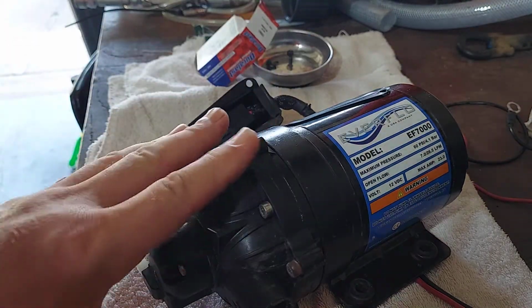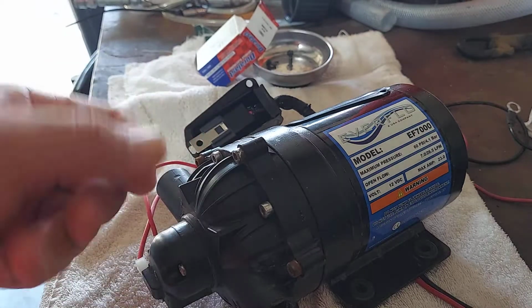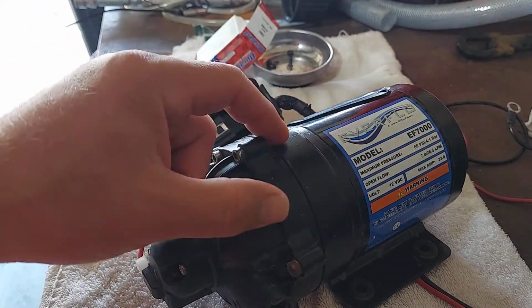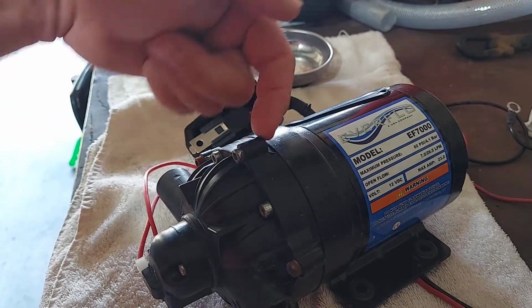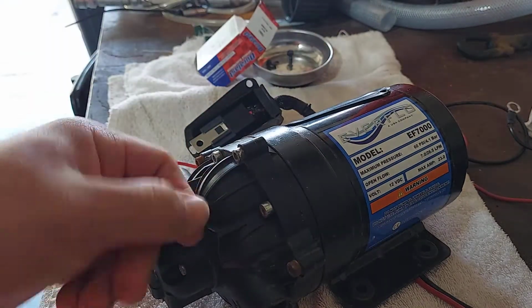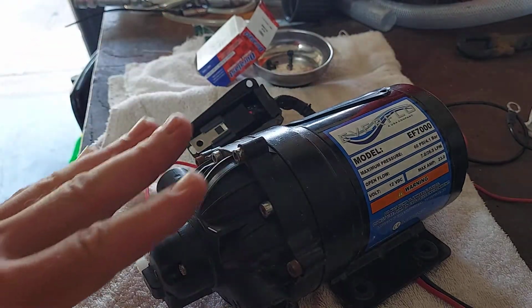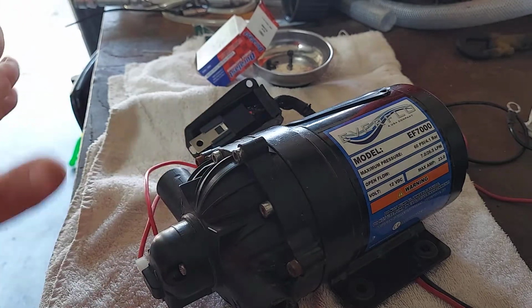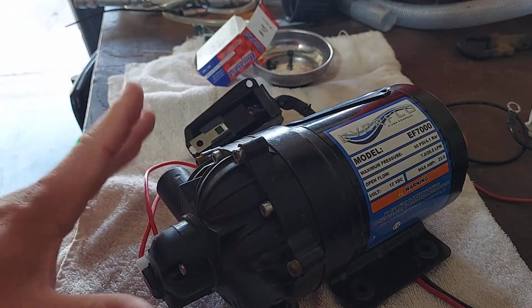I inspected all that and took it all apart. Nothing was torn, everything was moving, it was functional. I grabbed the shaft on the end of the motor that sticks out here — it was turning fine, the bearing was good, no leaks, no tears in the bearing seal, nothing like that. So I'm like, okay, what's next?